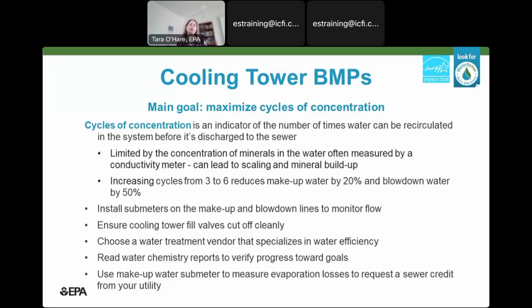Basically the water that's full of minerals is sent down the sewer, that's called blowdown, and then water is added to the system to make up for that water that was removed. So you want to install submeters on both the makeup and blowdown lines of your equipment to monitor how much flow is happening. This can also help ensure that the fill valves cut off cleanly, so they're not just trickling when they should be off.